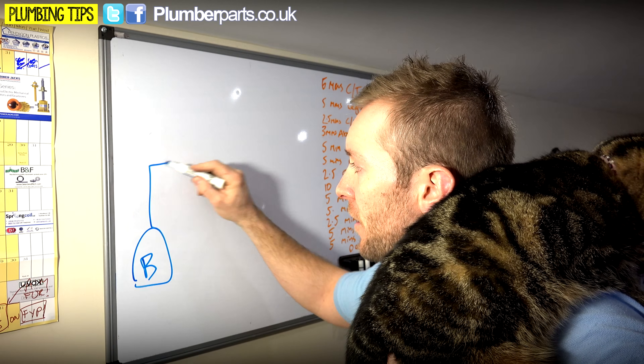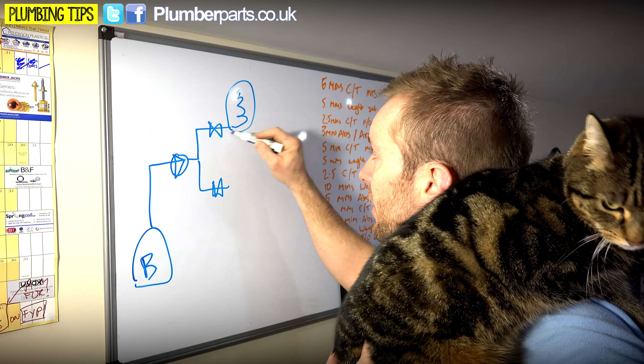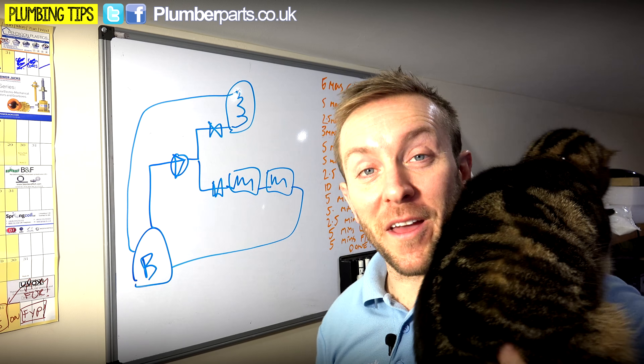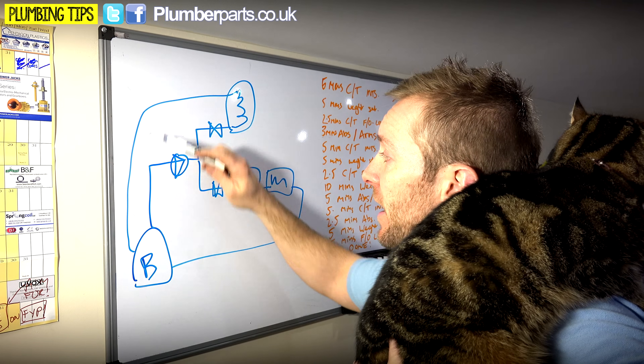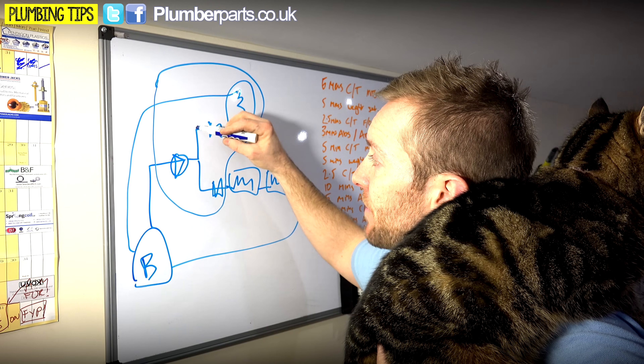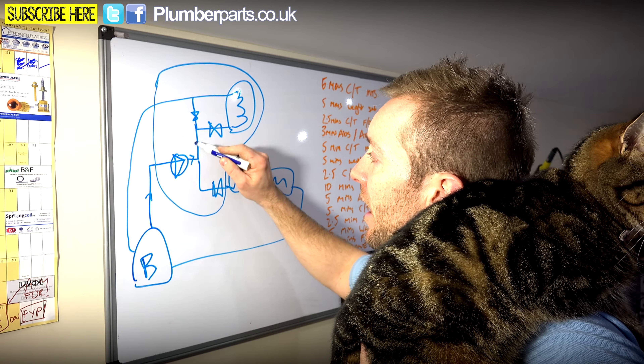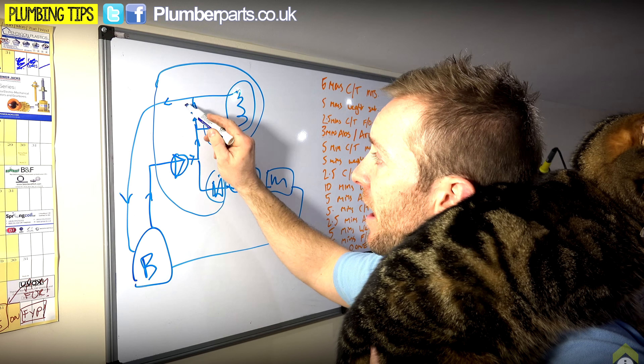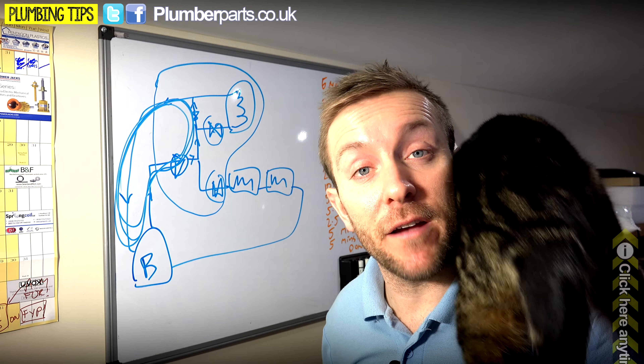So we've got our boiler here, flow coming out of it, our pump, our two-port valves — one going to the coil in our cylinder and back to the boiler, and one going to the radiators in the house. A nice little two-pipe system. The bypass has to go back onto the return. Usually the easiest way is that this part is all in the airing cupboard together. So you T into this piece here, put your bypass valve on there, and then up. Water comes out here, out here, up here — so if this valve shuts or this valve shuts, water can carry on going up the bypass and back around, giving you a constant circuit of water regardless of what these two valves or any of the thermostatic radiator valves on the system are doing.